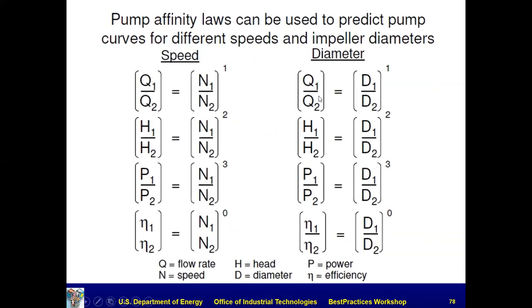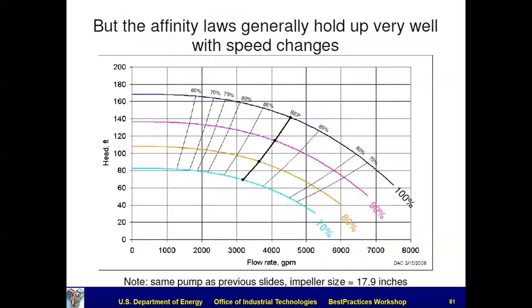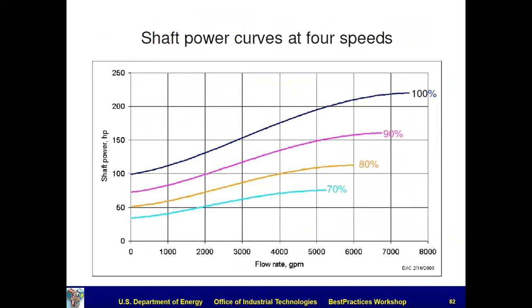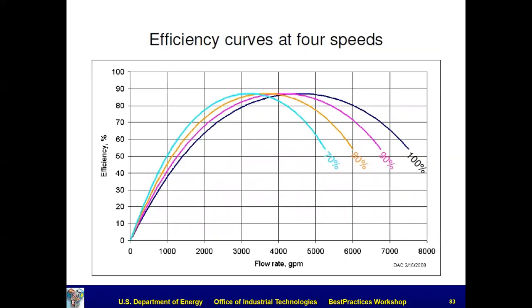Now, if I keep the rotational speed the same and do diameter changes, all of this column assumes the diameter is the same, and all of this column assumes that the speed is the same and I'm changing the diameter. So you see it's analogous in terms of the affinity laws to diameter. But as we said earlier, it tends to work better with speed changes than diameter changes. That's how the power curves change. That's how the efficiency curves change.